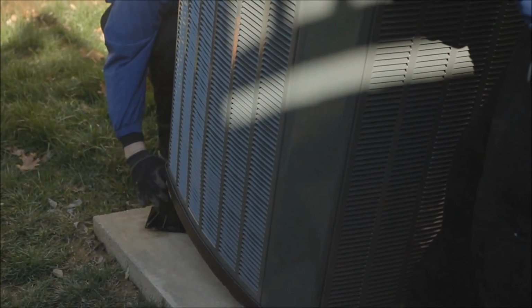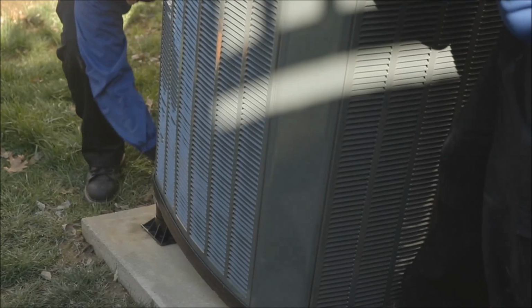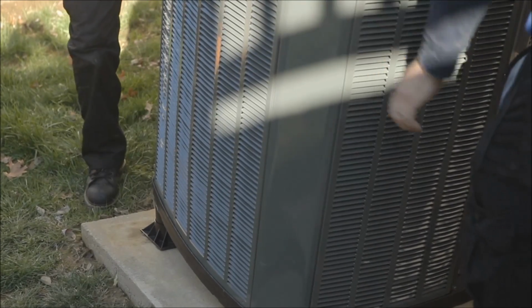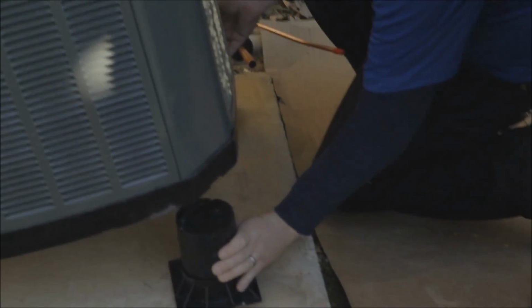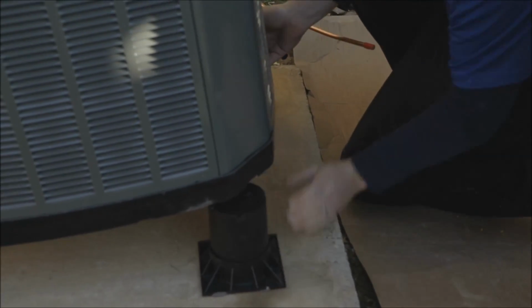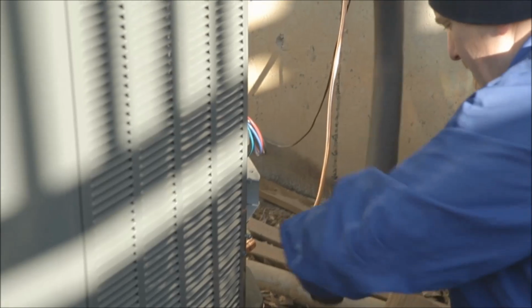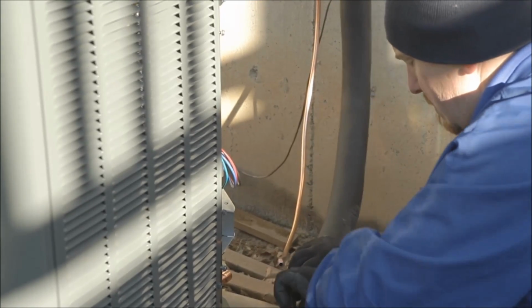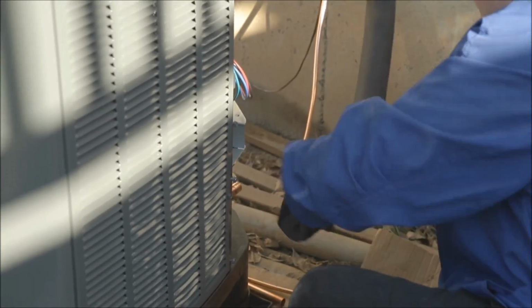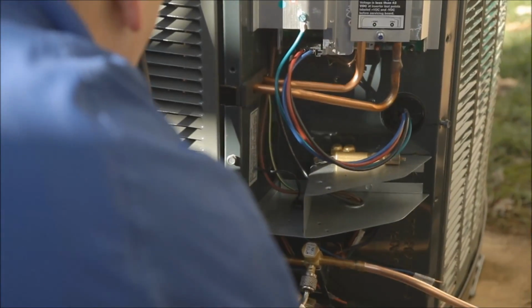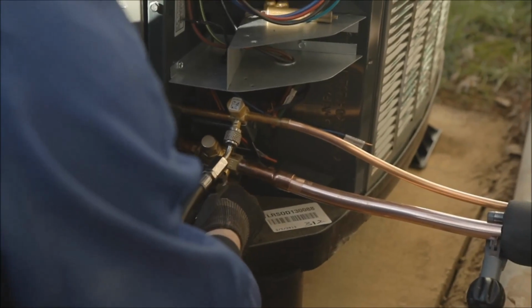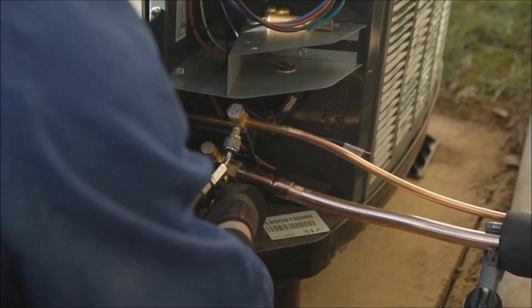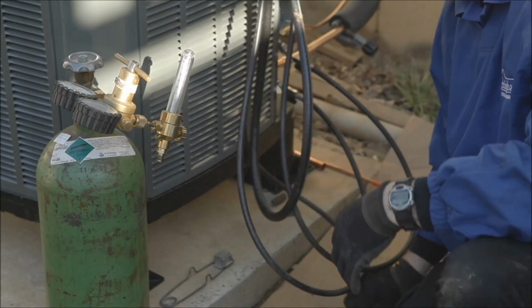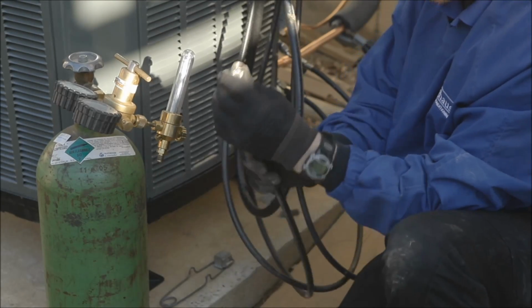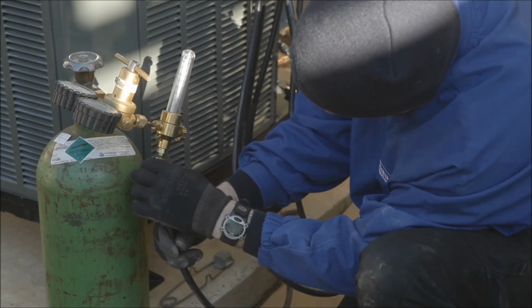Once the equipment is on the pad, snow legs are installed to elevate the unit. They raise the unit off the ground in areas that may have snow so the unit can drain properly during defrost cycles. To prepare for brazing, the technician cleans both the interior and exterior surfaces of the copper tubing. Using nitrogen allows the technician to braze the connections without creating excessive contamination from copper oxides during the braze process. Omitting this step could contribute significantly to reduced performance and reliability of the installed equipment.